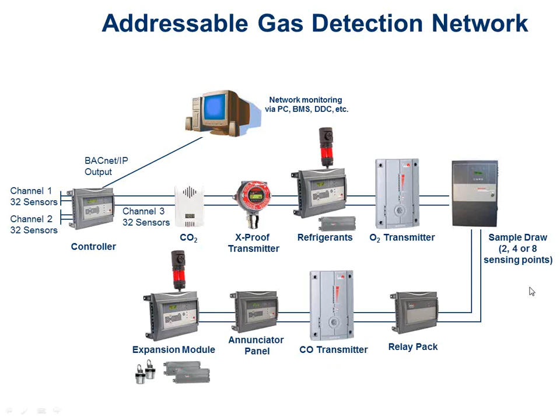Sometimes you can have communicating gas detection systems like I'm showing you here, where the sensors can communicate back to the main panel, and that can communicate to your BAS, and it can even communicate to your strobes and stuff like that. That's not super common. Usually we have one sensor with one strobe and that kind of thing, but if you have a large system with lots of stuff going on, you may want to choose this type of thing. Right, and here we got all kinds of mix of stuff. We got sensors that go in space, we got sample draw systems that have the pneumatic tubes, we got annunciation panels, all kinds of things.